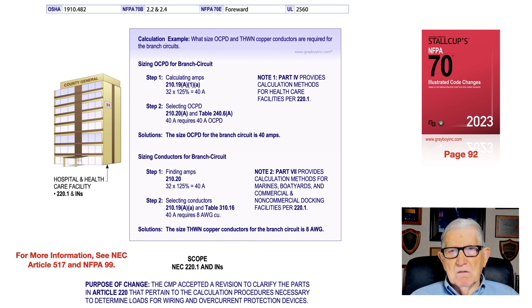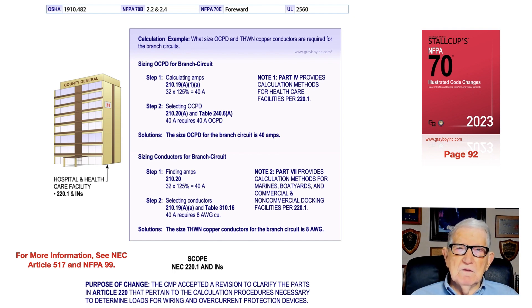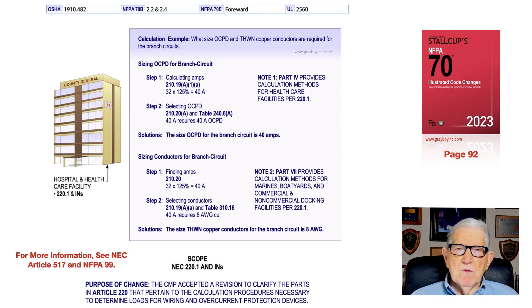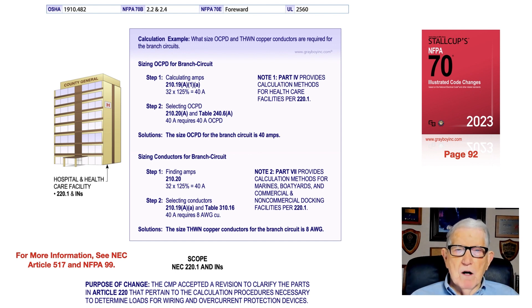It would be 100 percent of 32 amps if it wasn't a continuous load operating less than three hours. Step two is applying and sizing the overcurrent protection device. We select, based upon step one, 40 amps from table 240.6(a), and we pick up a 40-amp overcurrent device. So the solution is: a 40-amp overcurrent device is required.